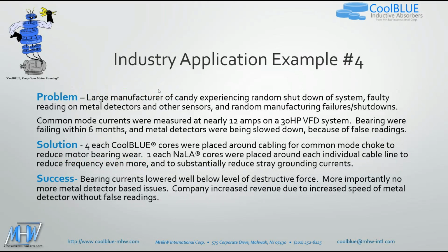Application example 4, a large manufacturer of candy experiencing random shutdowns of their system, faulty readings on metal detectors and other sensors, and random manufacturing failures and shutdowns. The common mode currents were measured at nearly 12 amps on a 30 horsepower VFD system. Bearings were failing within 6 months. Metal detectors were being slowed down because of the false readings.